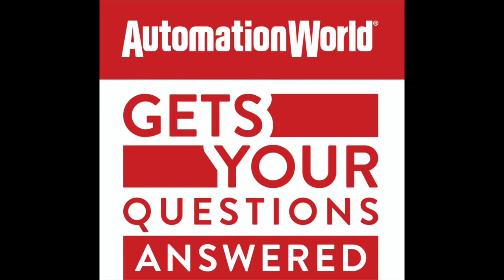So let's move on now to mean time before failure. What does that mean? Yeah, so another one where if you break down the acronym, it helps you a lot. I do hear this both as mean time before and mean time between failures, but essentially it's getting at the same thing, right? Which is how long it takes between specific downtime events for a piece of equipment. So if machine A goes down and then comes back up at 12 noon, the line runs a while, but then it goes down again at 3 o'clock. That's 3 hours between those two failures of that machine.